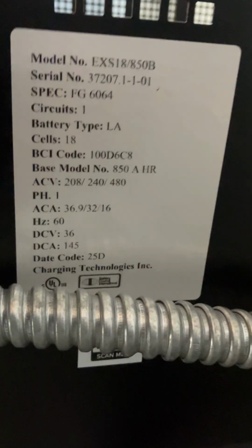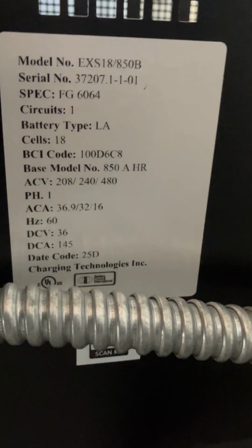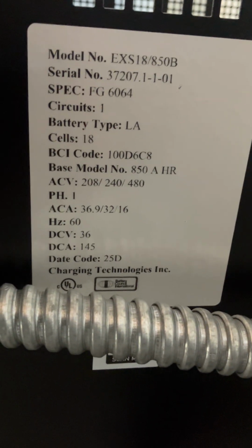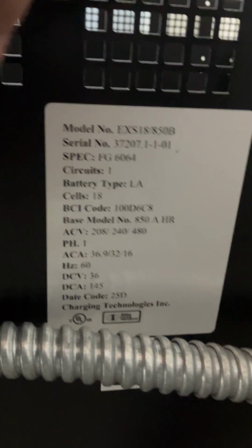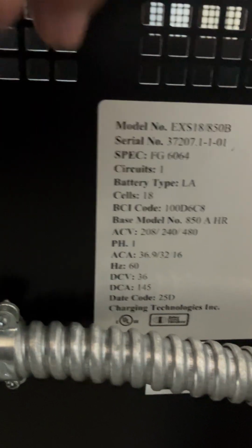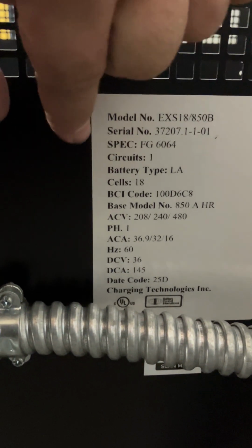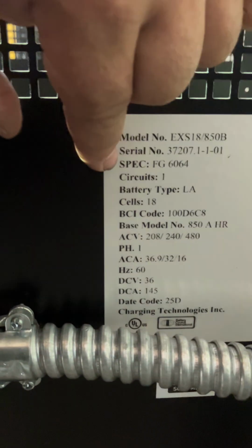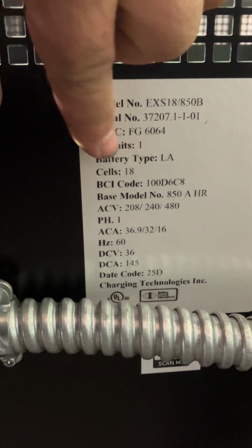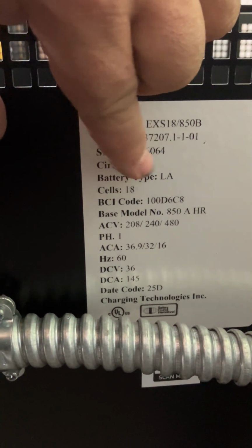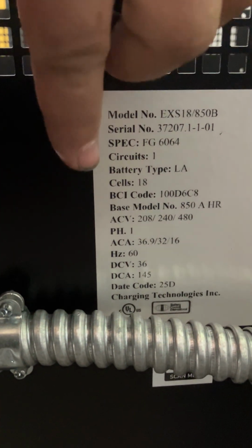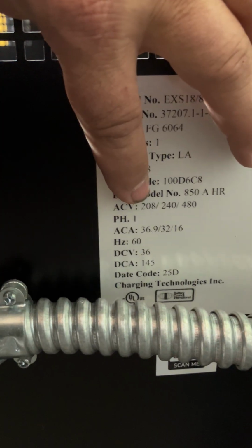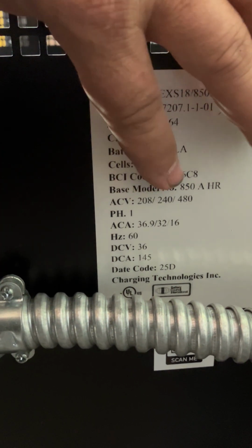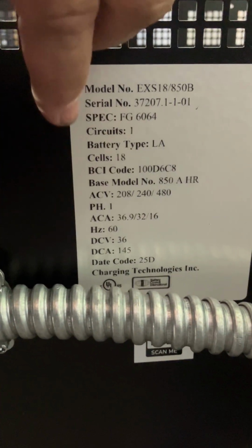All right. So whenever you're hooking up a piece of equipment you're not all that familiar with, find the sticker here that has the electrical information. Now, much of that information is not at all important to me as the electrician. But down there somewhere, there's AC voltage, and it shows three possibilities: 208, I think the other is 240, and then 480. Down below that is phasing, which shows one, so this is single phase 208, single phase 240, single phase 480. Those are the three voltages that it can run on.